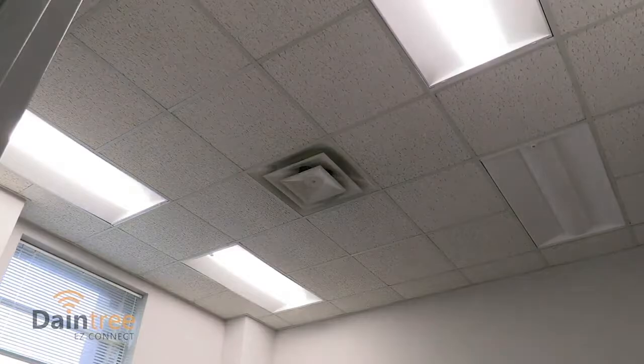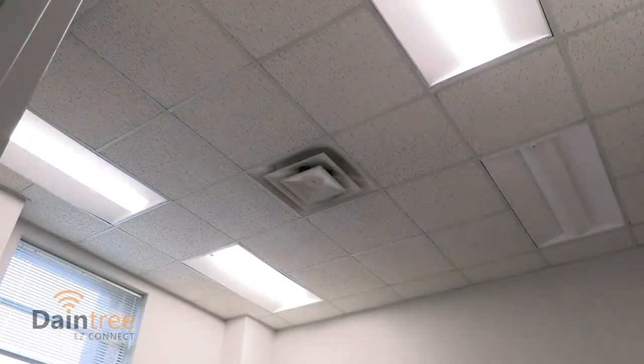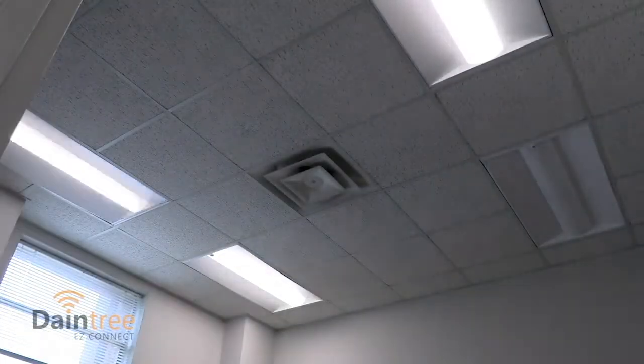The best time to do this is when it's completely dark, but it's okay to do it at any point in time. And so what these lights are doing is they're going through a process of measuring the light below each fixture and creating a set point so that once the daylight harvesting is operating, it will dim the fixtures.